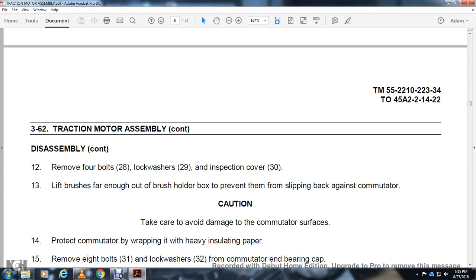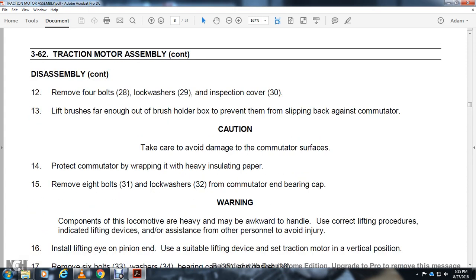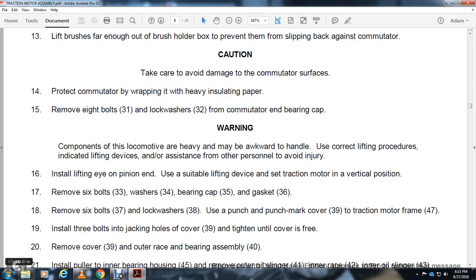Remove 4 bolts 28, lock washer 29, inspection cover 30. Lift the brush far enough off the brush holder to prevent it from slipping back against the commutator. Caution: take care to avoid damage to the commutator surface. Protect the commutator by wrapping with heavy insulating paper. Remove 8 bolts 31, lock washer 32, commutator end bearing cap. Use the lifting eye on the pinion end. Use suitable lifting device to set the traction motor in a vertical position. Remove 6 bolts 33, washer 34, bearing cap 35, gasket 36.